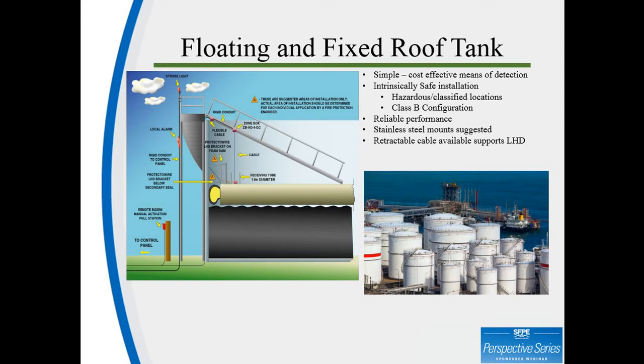Fixed-top floating roof tanks and fixed roof tanks are often protected the same way, despite the fact that there's a floating roof enclosed within the tank. For these tanks, the most common location for detection is around and over any of the vents within the tank. Should the air inside become hot, this will activate the detector and initiate an alarm. Regardless of the tank type, many of these locations are classified, so the use of intrinsic safety barriers may be necessary.